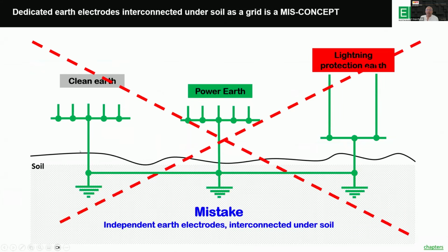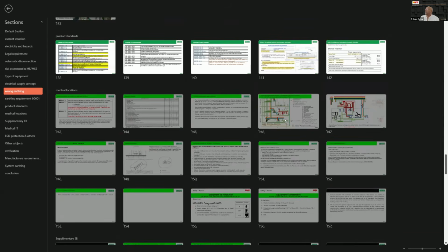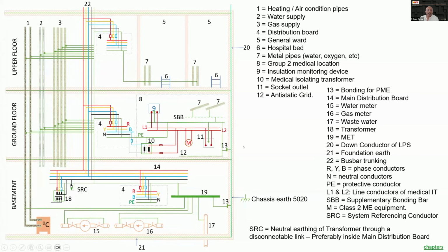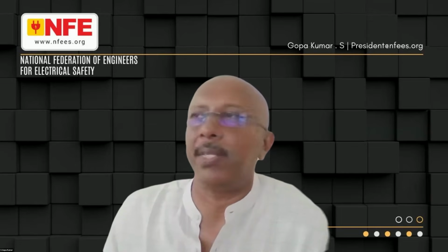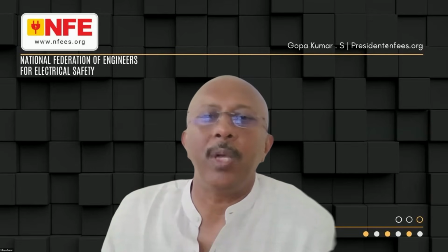So the subject of earthing is not about making a lot of earth pits. The subject is about this one. Let me show you the correct picture. This is the correct way of earthing. You can find this picture in the National Electrical Code of India 1985 and National Electrical Code of India 2011. Unfortunately, in the 2023 edition, this picture is removed. But this information is also a part of the NFE guide on electrical safety audits in hospitals. So please have a look at these documents. You can find this particular picture, and this is how you must do earthing.